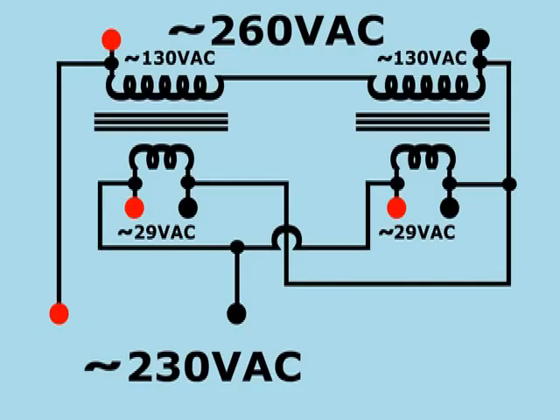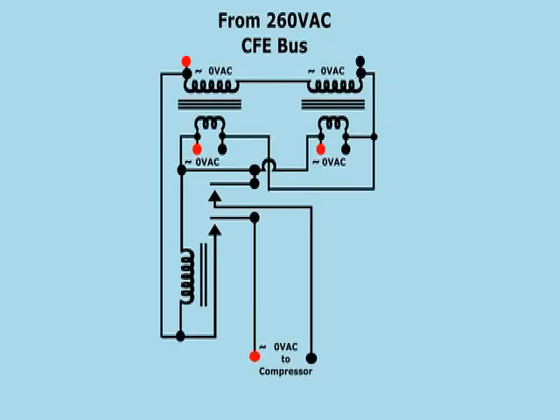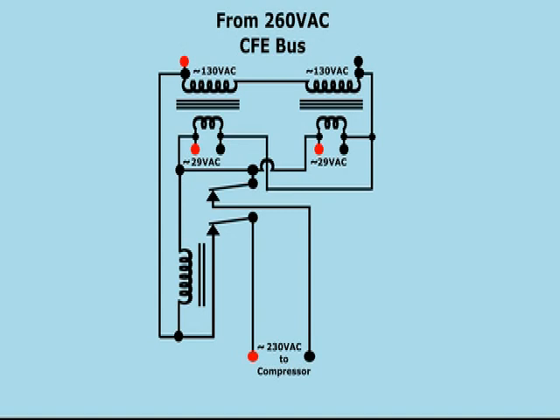The step-down transformers have their primaries permanently connected in series to the 260-volt alternating current bus line that comes from the power company. The secondaries of these transformers, wired in parallel, are connected in such a way that the voltage they deliver is subtracted from the power company line voltage, in order to deliver a more appropriate voltage to each compressor. This is achieved by means of a contactor which connects the output of its corresponding voltage reducer. Only power company line is live.